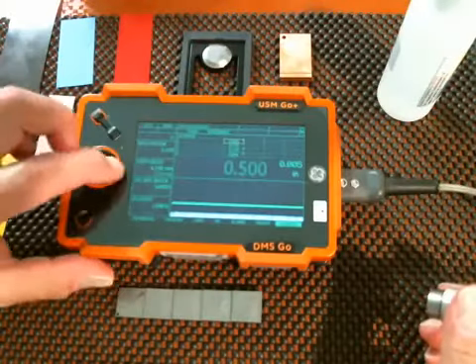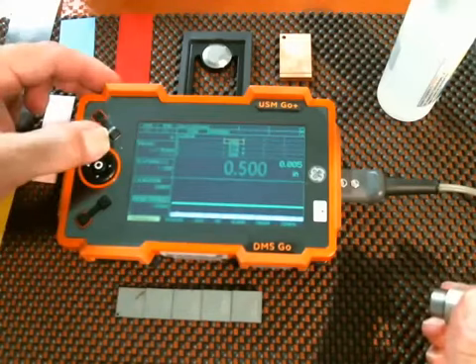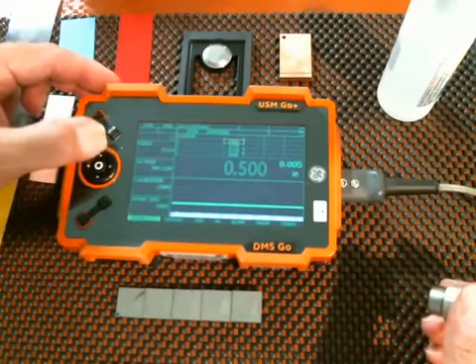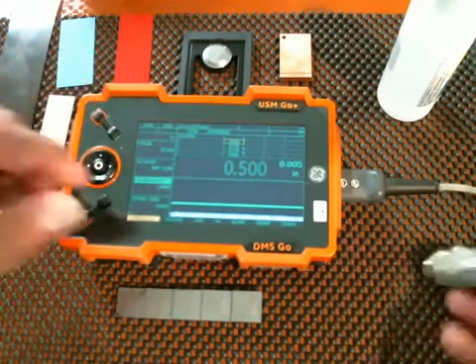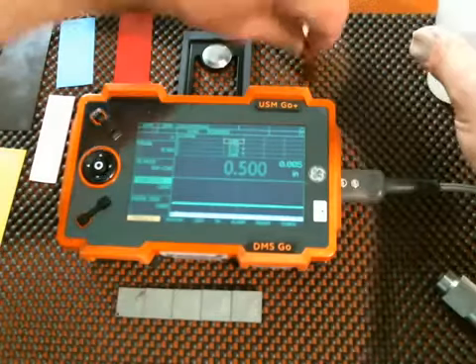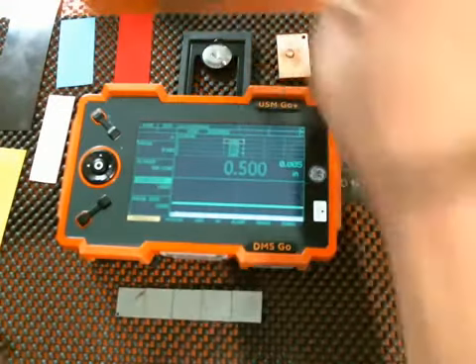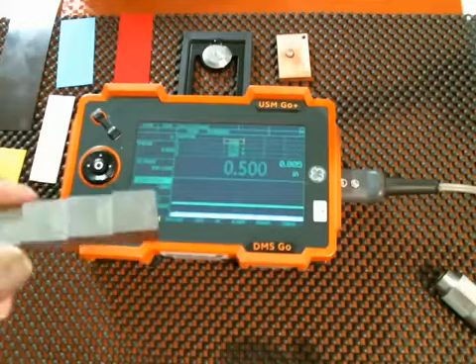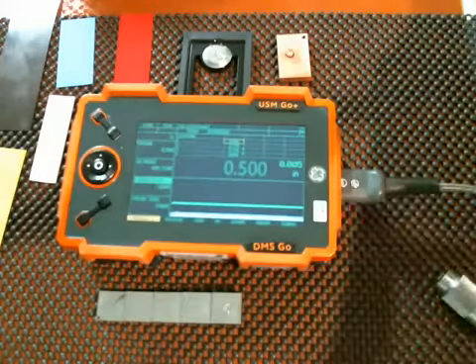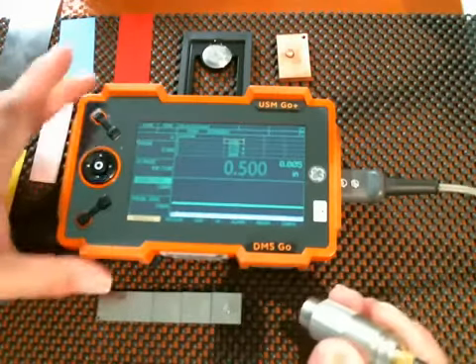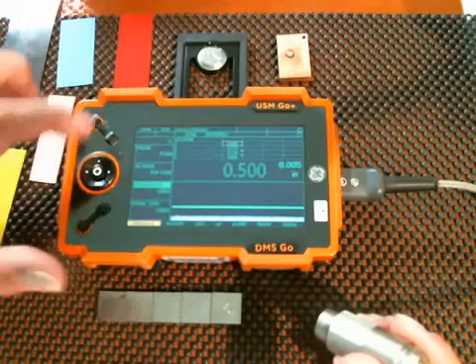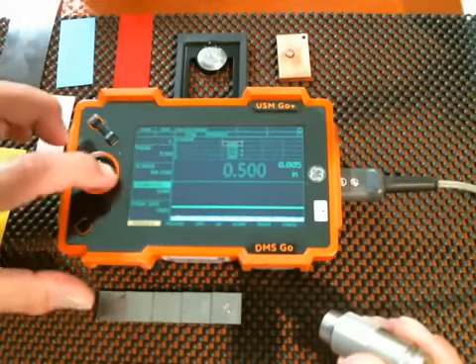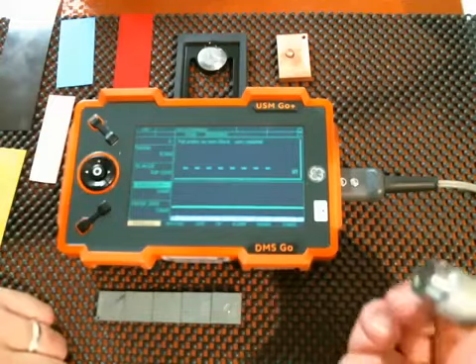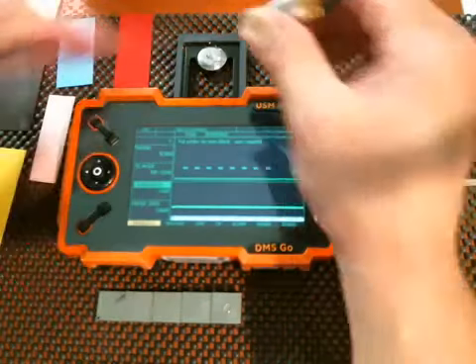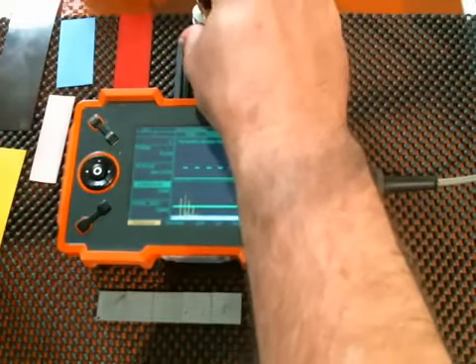Go back to the Probe and Cal menu. Scroll up to Calibration. And now put a drop of couplant on our blocks. I also have a standard 5-step calibration block here. Put a drop on my 1/2-inch step. Okay. So at this point, we're ready to begin our calibration. On the Probe and Cal menu, we scroll to Calibration, right arrow to start. The first instruction is to put the probe on the zero block. That's the one built into the kickstand, using couplant. Stay coupled. Remove the probe.